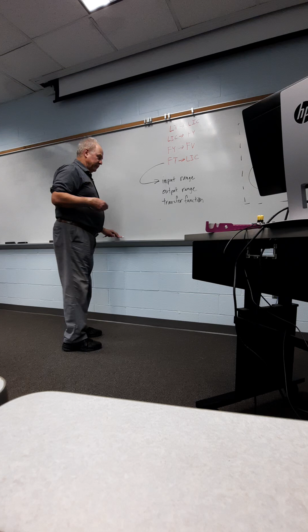So if we pick on any one thing, I'm going to pick on level transmitter, for instance. You have a level transmitter function. What's the general input into this level transmitter? Tank level. What's the output? Well, we know the output goes to the computer. It's electrical. So it's going to be something like a current loop. I'm going to say 4 milliamp to 20 milliamp current loop. I'm going to assume that for everything electrical, because that's actually what we use out there.